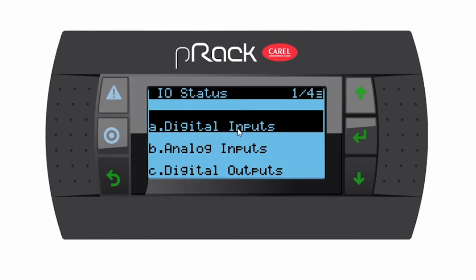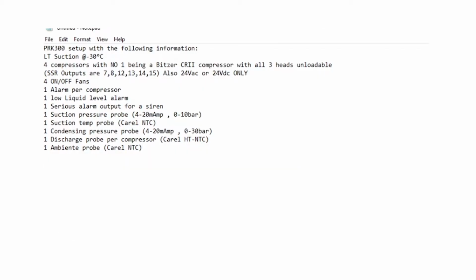But remember, when we are configuring a pRack controller, we need a wiring diagram or some sort of notes. So I compiled a note for us. It's going to be a low temp suction running at minus 30 degrees Celsius. 4 compressors, with number 1 being a Bitzer CR2 compressor with all 3 heads unloadable. And remember, the SSR outputs on the pRack controller are outputs number 7, 8, 12, 13, 14 and 15. And also they are 24 volt AC or 24 volt DC only. You can't connect 220 volts to them.